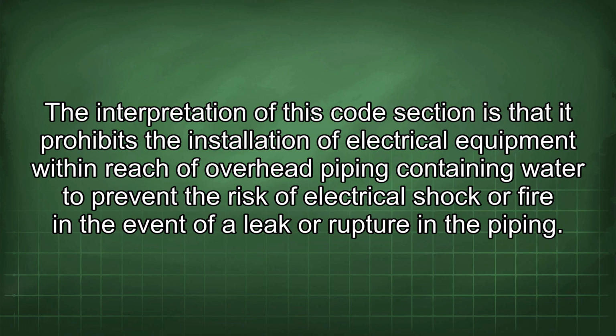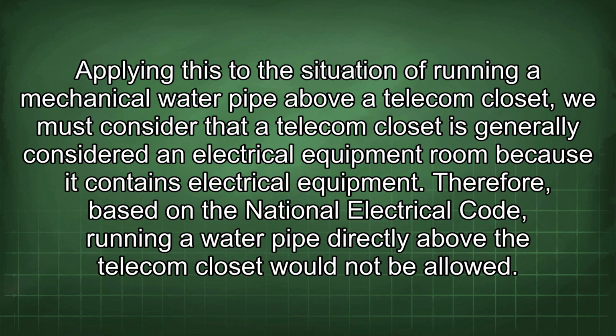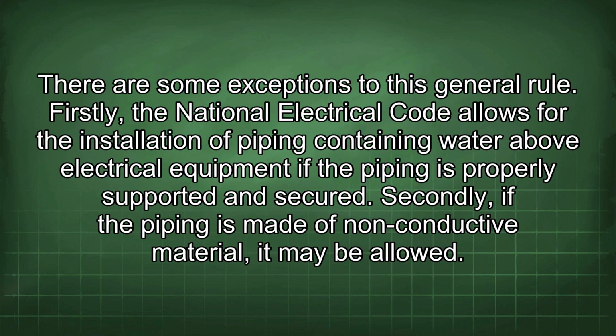the piping. Applying this to the situation of running a mechanical water pipe above a telecom closet, we must consider that a telecom closet is generally considered an electrical equipment room because it contains electrical equipment. Therefore, based on the National Electrical Code, running a water pipe directly above the telecom closet would not be allowed. There are some exceptions to this general rule.